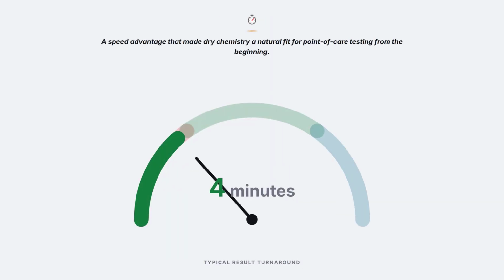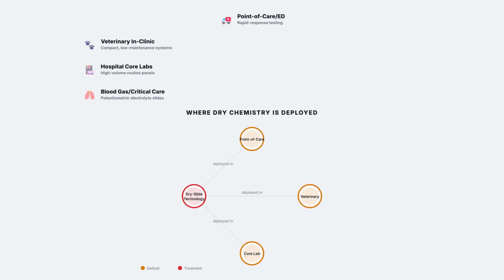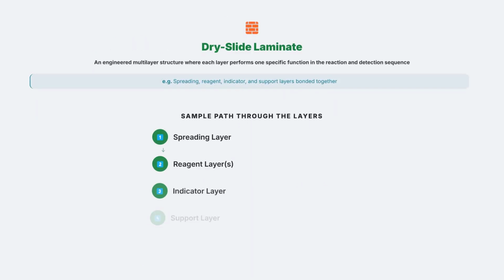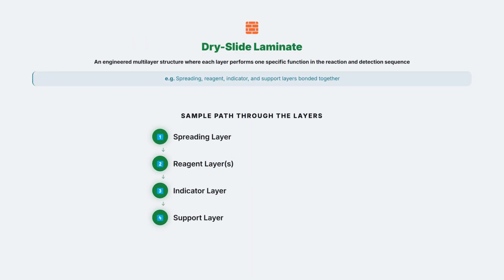A typical dry slide colorimetric result develops and reads in under 5 minutes from sample application, a speed advantage that made the technology a natural fit for point-of-care and rapid response testing environments from the beginning. Where this technology actually lives today spans a wide operational range: point-of-care and emergency department analyzers, veterinary in-clinic chemistry systems, some hospital core laboratories running high-volume routine panels, and blood gas and critical care analyzers using the potentiometric electrolyte variant specifically.